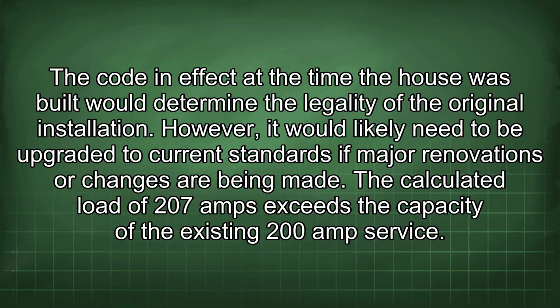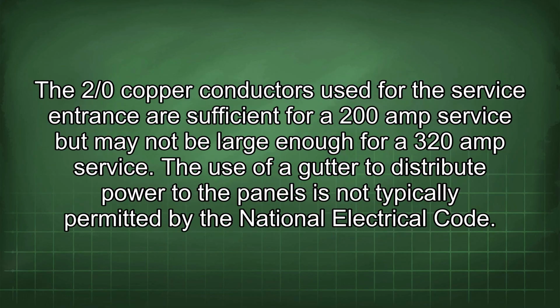The calculated load of 207 amps exceeds the capacity of the existing 200 amp service. The 2/0 copper conductors used for the service entrance are sufficient for a 200 amp service but may not be large enough for a 320 amp service. The use of a gutter to distribute power to the panels is not typically permitted by the National Electrical Code.